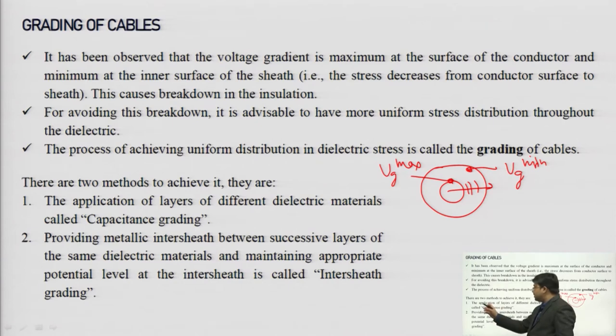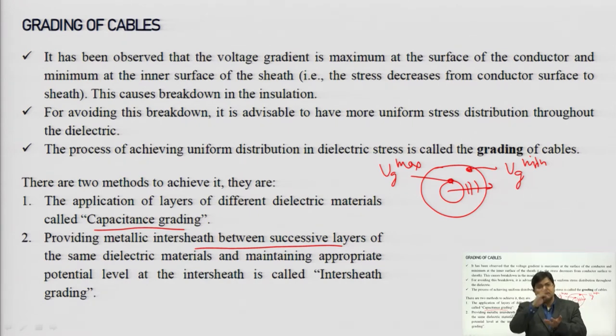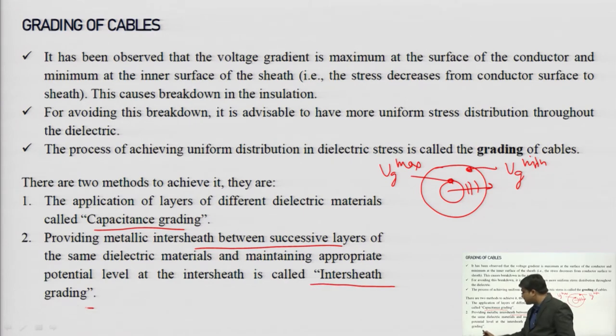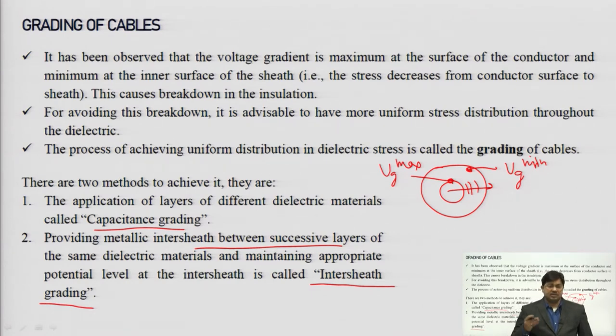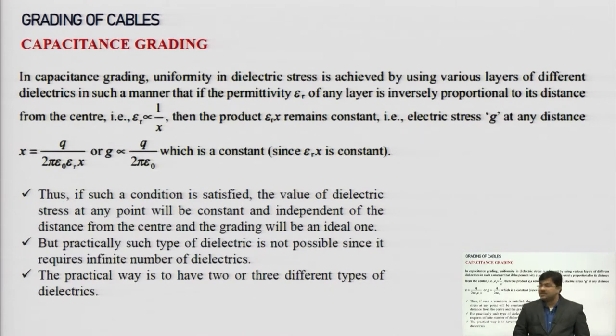The first method is the application of layers of different dielectric materials, called capacitance grading. The second is providing metallic inter-sheaths between successive layers of insulation — instead of a single sheath, multiple sheaths are provided between successive insulation layers. This is called inter-sheath grading.